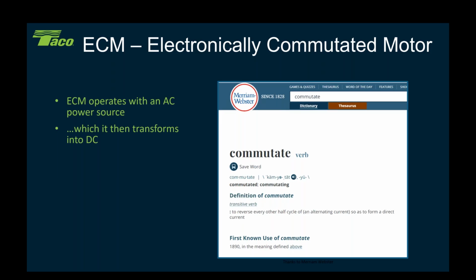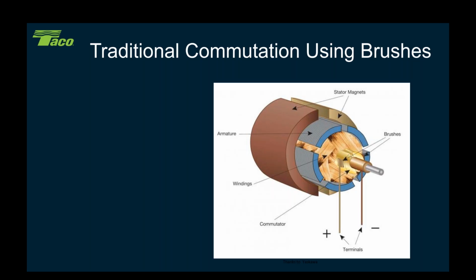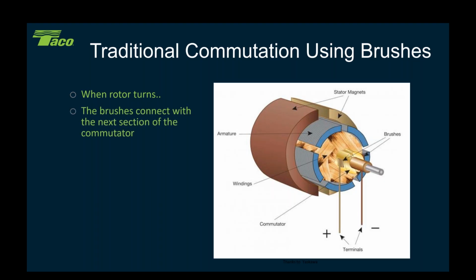The difference is that in an ECM motor, we're going to take that AC power and turn it into DC inside the motor. And inside there, everything is DC. Once you get past the AC connection, go through the speed controller, everything else is DC inside that motor. So it's a different style motor than an AC induction motor. So when the rotor turns, the brushes connect with the next section of the commutator. And this is a conventional DC motor that has brushes in it.